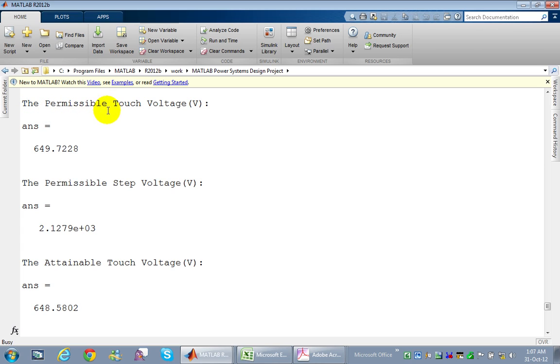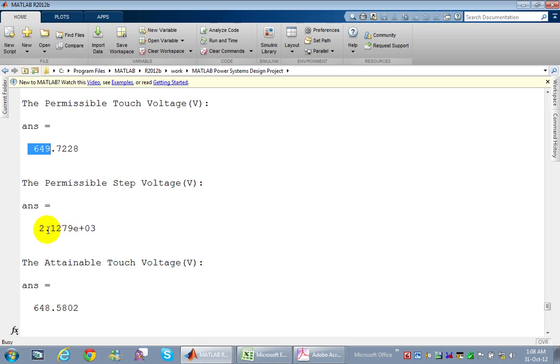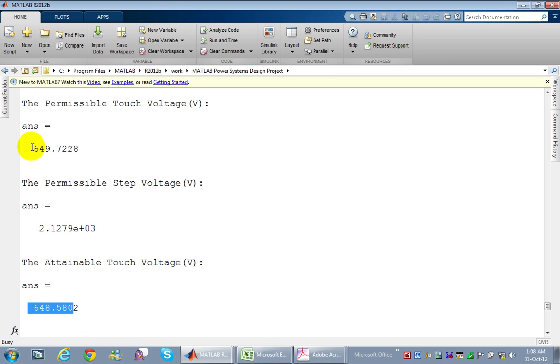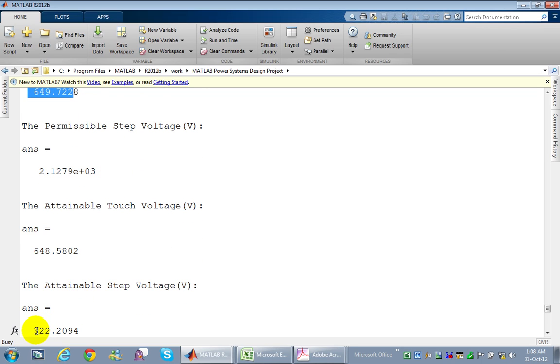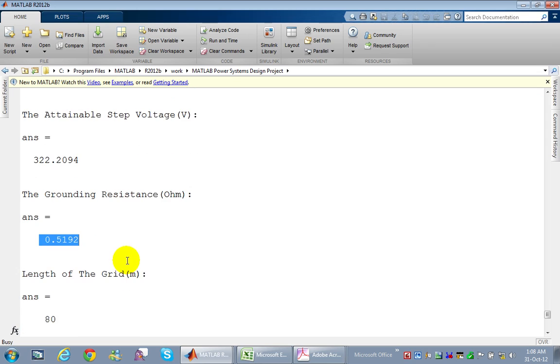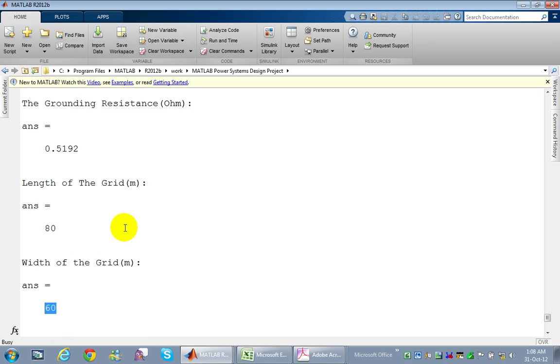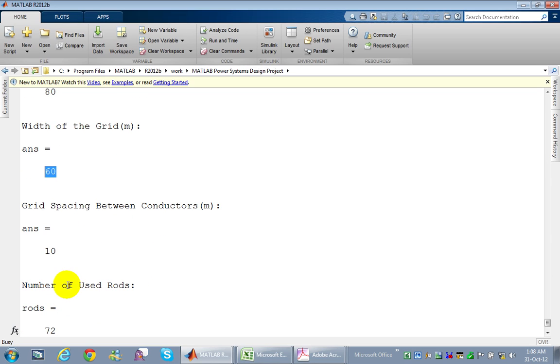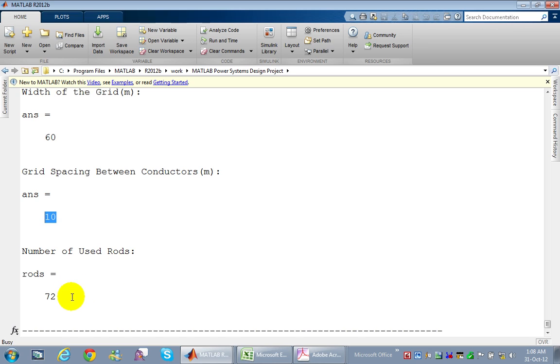The permissible touch voltage is approximately 650 volts and the permissible step voltage is around 2,100 volts. The attained touch voltage is 648 volts, which is less than the permissible value, and the attained step voltage is 322 volts, also less than permissible. The grounding resistance is 0.5 ohm. The grid is 80 by 60 meters with conductor spacing of 10 meters, and 72 rod electrodes are used.